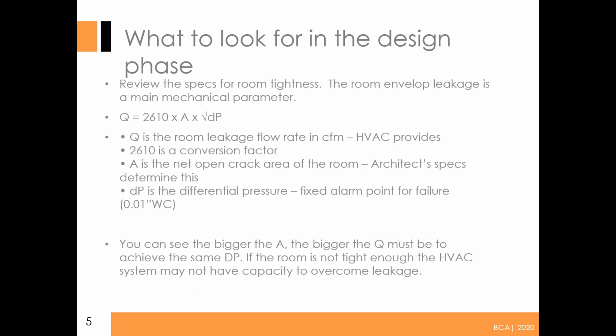So the other thing I want to talk about is tightness, and I'm showing a formula up there, but I don't want you to get too concerned about it. The main thing is that this is often what's used, and it's not really a calculation that you can actually perform, because the A, which is the crack area, is so hard to determine. It's got to be kept to the lowest by the architect's spec. And if they don't, then the Q, which is usually our side, the HVAC side, has to get bigger.